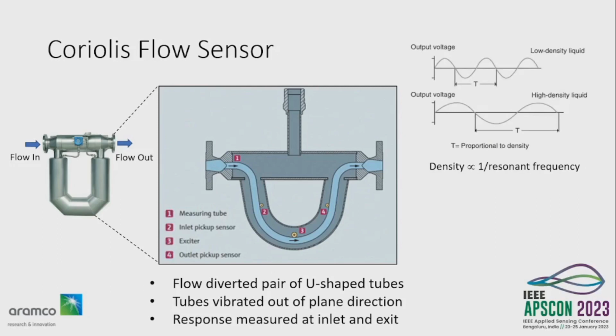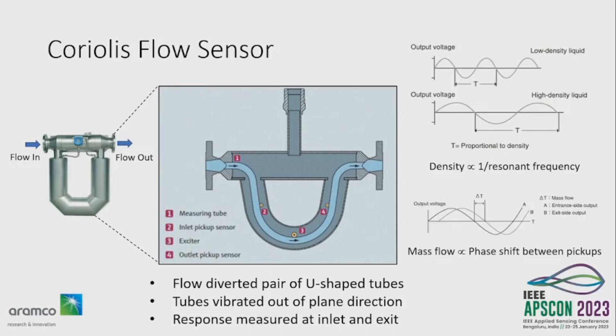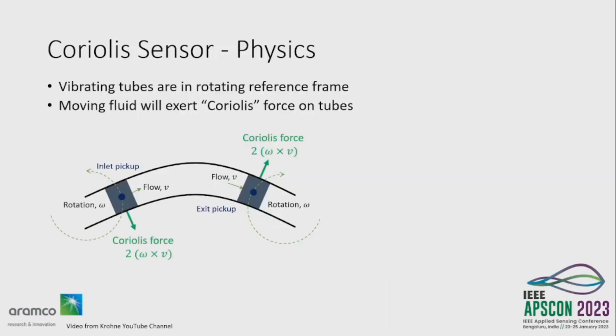So very simply, you can get two measurements from this sensor. One is the density of the fluid flowing through the U-tube, and that's related to the resonant frequency. The higher the frequency, the lower the density of the fluid. The second measurement you can get is the mass flow of the fluid, and that's related to the phase shift that you will see in the vibration response between the inlet and the outlet. The larger the phase shift, delta T, the higher the flow rate is. So fairly straightforward.